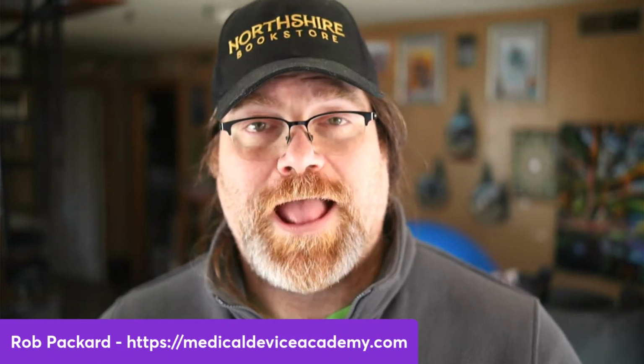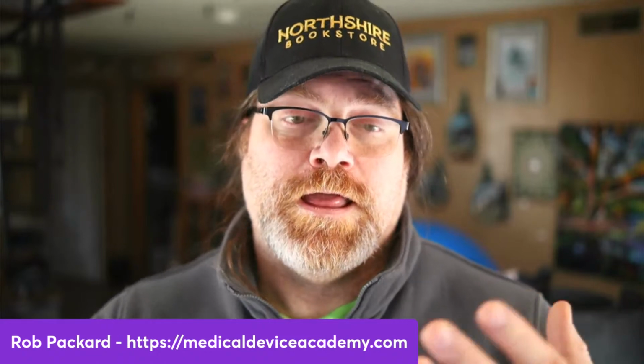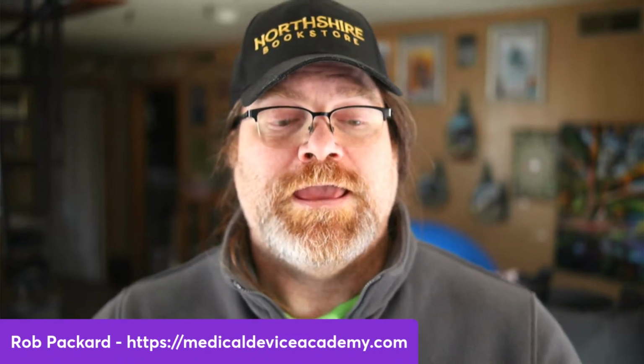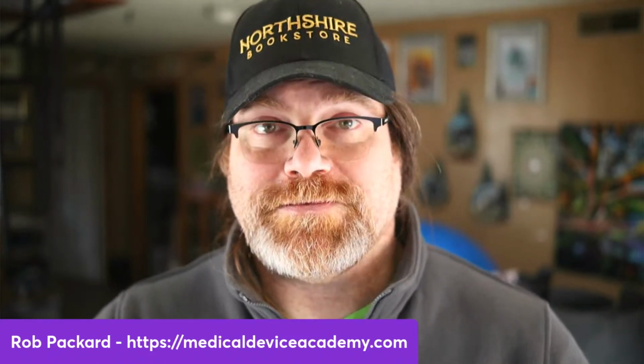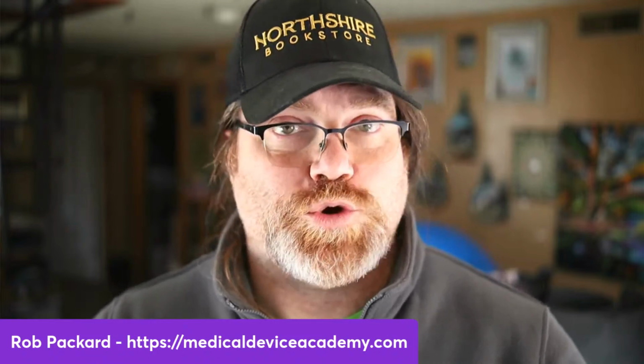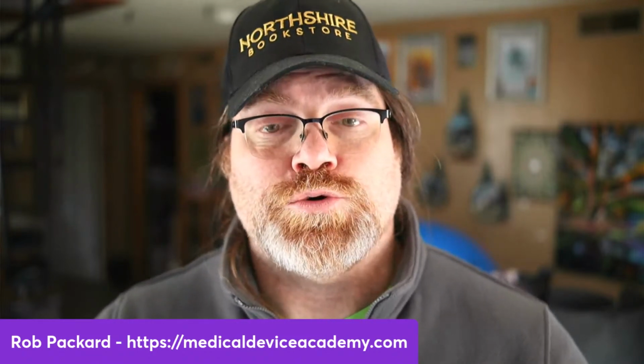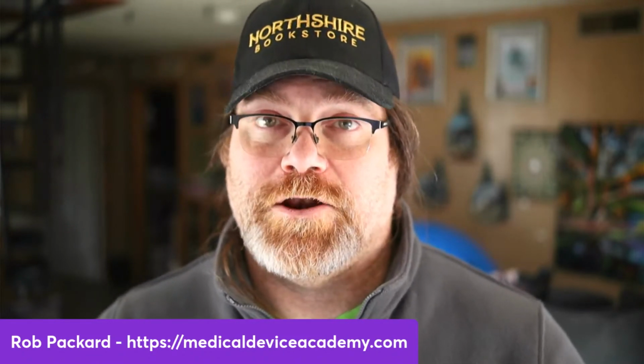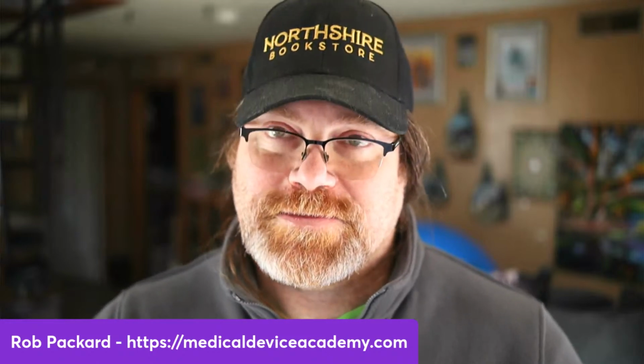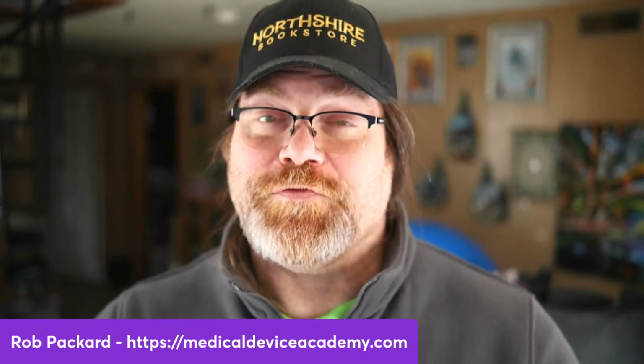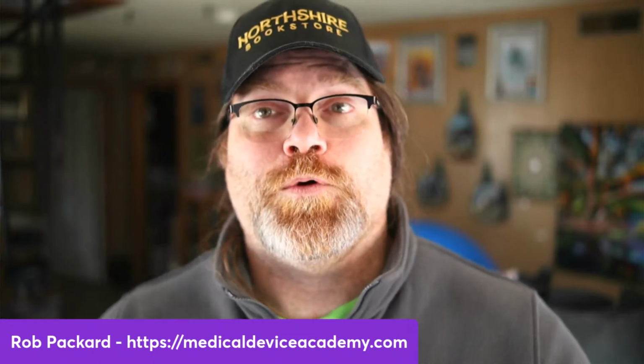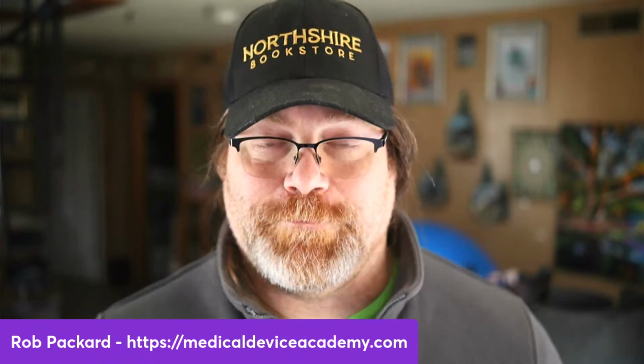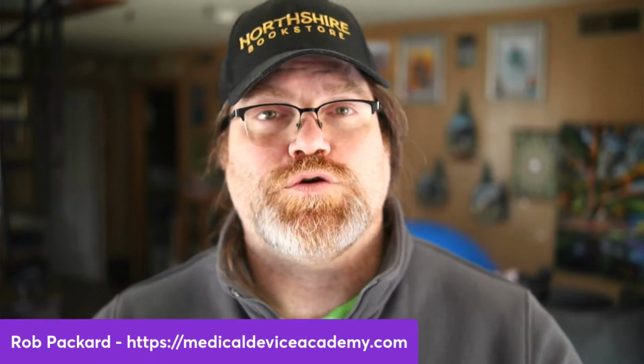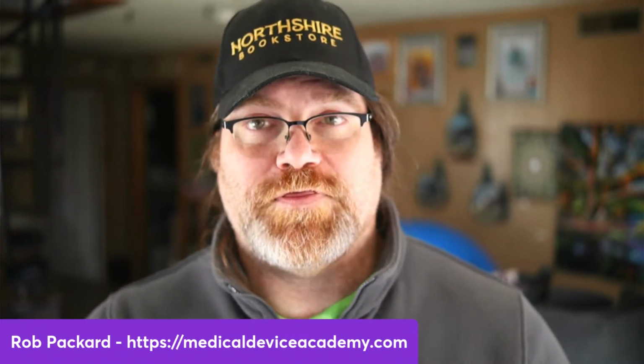So if you think about the things that you want to ask in a pre-sub that are absolutely critical, number one thing you want to look at is anything where I might have to repeat the testing and pay for it twice, because that's just a waste of money. Number two, anything that might take more than 180 days. And the third thing is anything where I might have to make samples and I have to do it in batches rather than one-offs.